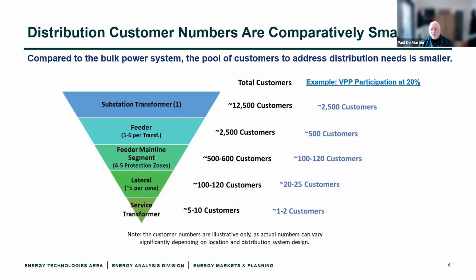The feeder is typically broken into multiple protection zones, where reclosers isolate faults to restore customers more quickly - you may have 500 to 600 customers in one of those segments. A lateral coming off the main line goes further down a street to tie into service transformers, typically serving 100 to 120 customers.